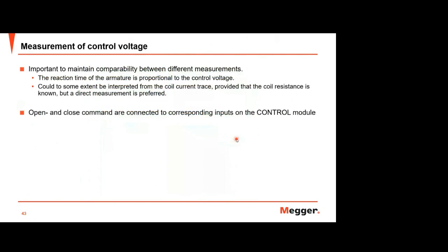And also measurement of the control voltage. This is an important point to maintain: compare the control voltage parameter. Because the reaction time of the armature is proportional to the control voltage, and maybe could to some extent be interpreted from the coil current trace, but direct measurement is meaningful. So even though this has correlation, if you have any issue from this testing, you need direct measurement to check your control voltage.